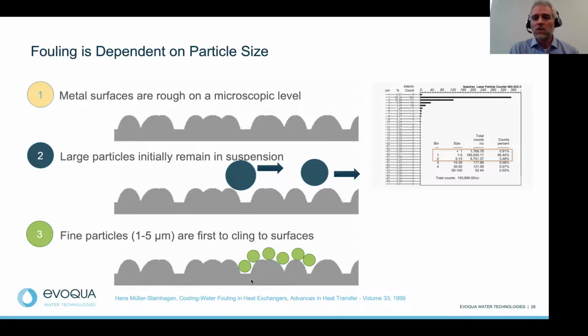And when you look at what's in a cooling environment, on the right-hand side of the screen here is a water sample that we ran through something called a particle size analysis. It's a test that allows us to understand more of the resolution of your water, right? I think you probably understand turbidity, you understand total suspended solids, but particle size analysis is a next level water quality analysis that really allows us to understand what your water quality is like and what type of technology you should be selecting. So this is the output of a water quality analysis from a particle size analysis.